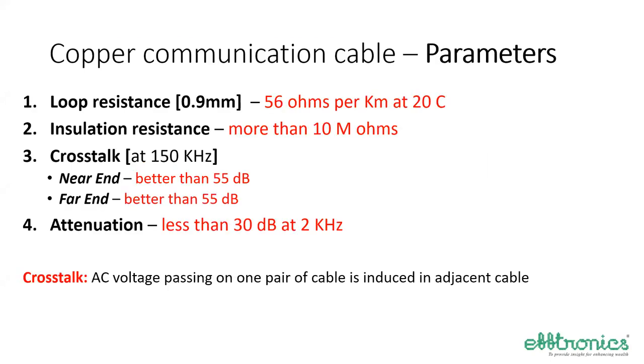Let us look at copper communication cable. Normally what we use is 0.9 mm cable, which has a loop resistance of 56 ohms per kilometer at 20 degrees. Insulation resistance shall be more than 10 megaohms if we have to use it for axle counters or for this purpose. Crosstalk shall be better than 55 dB at 150 kilohertz. And attenuation shall be less than 30 dB when used end to end for the axle counter purpose.